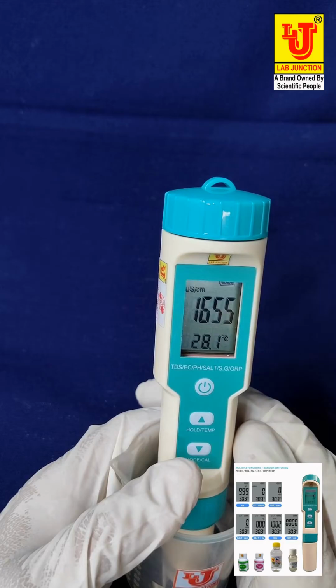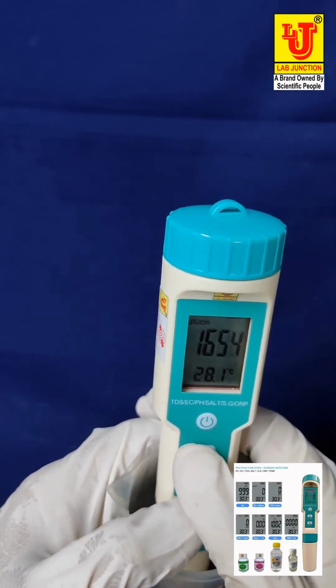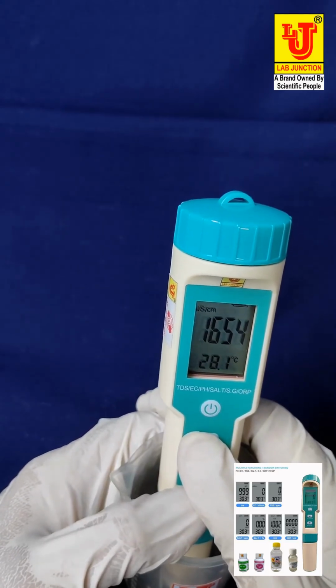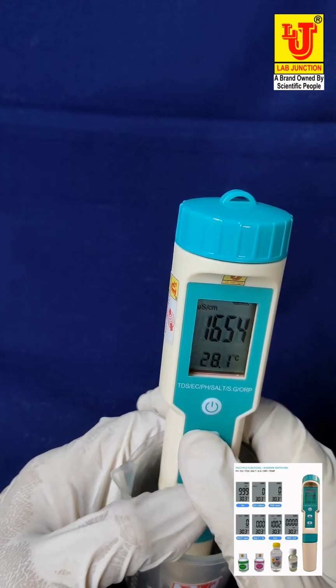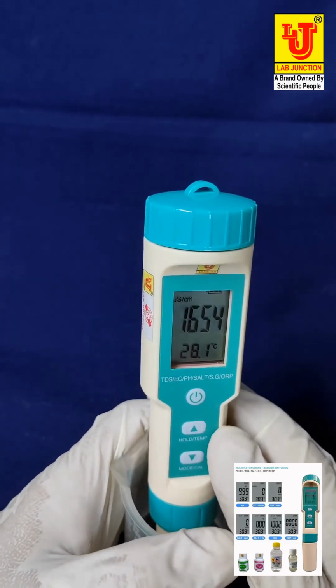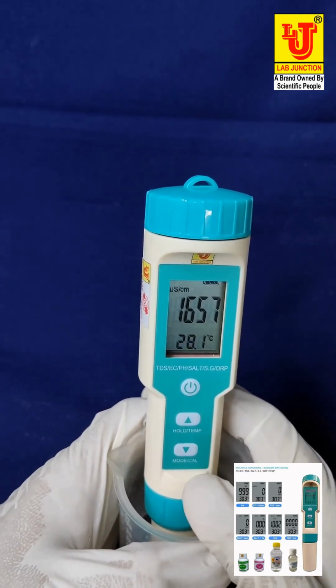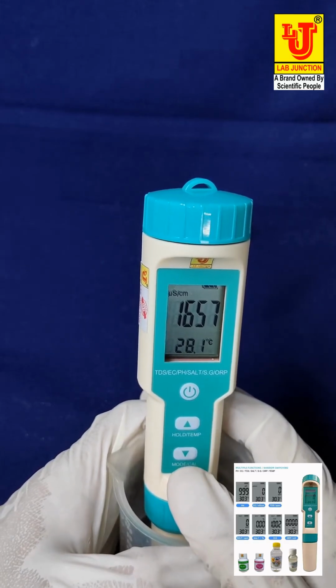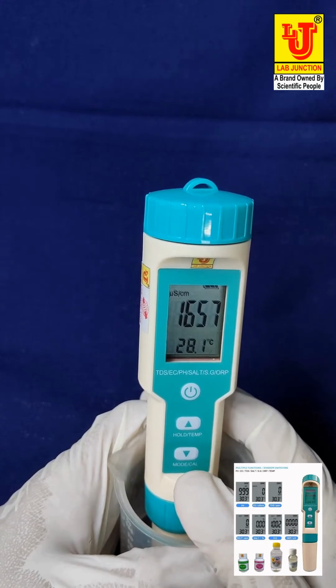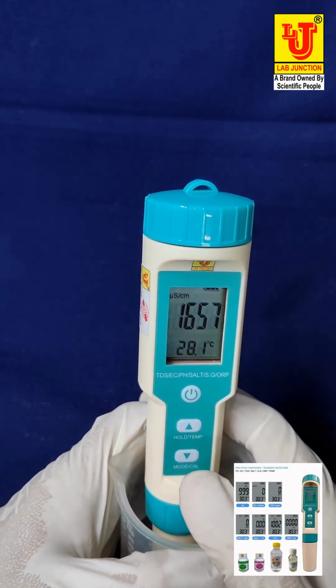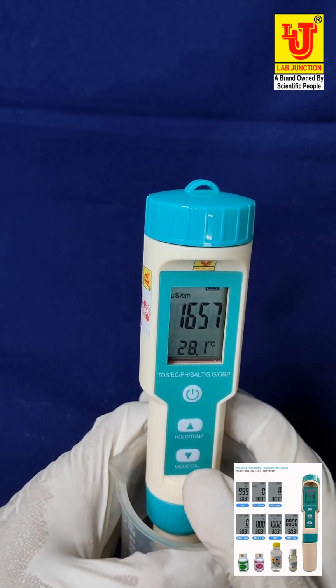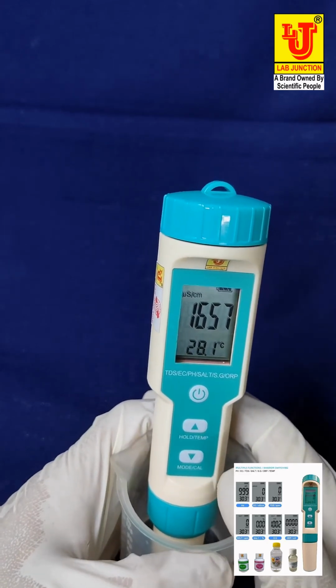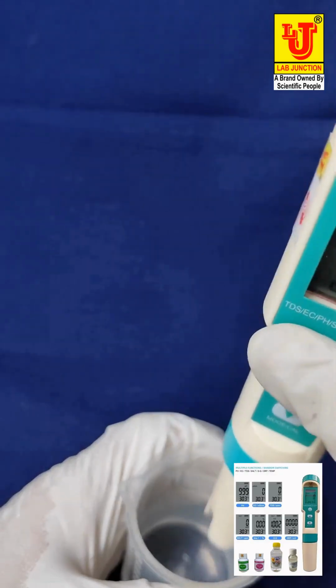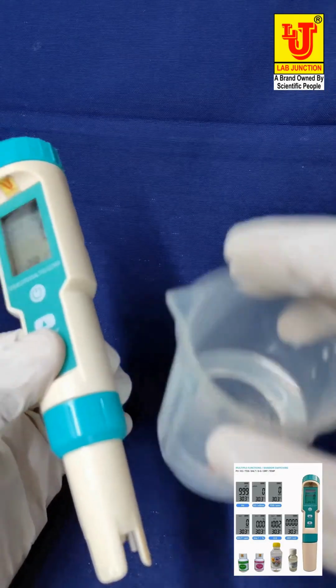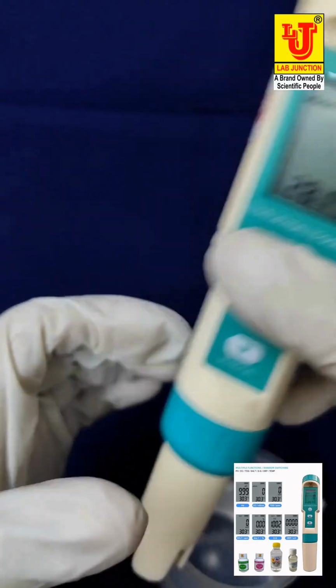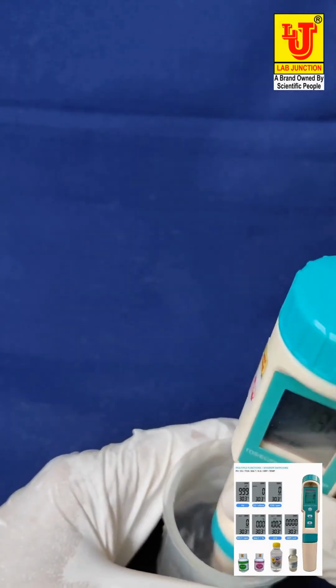Now this is calibrated. In this way, you can calibrate all parameters which are in this instrument like pH, TDS, conductivity, ORP, SG with the help of standard solution. You only have to press on that display parameter, press the cal key for 3 seconds, and after 3 seconds release the cal key. Automatically the instrument calibrates on that standard solution which you dip in the instrument. Again I am refreshing this with the distilled water.